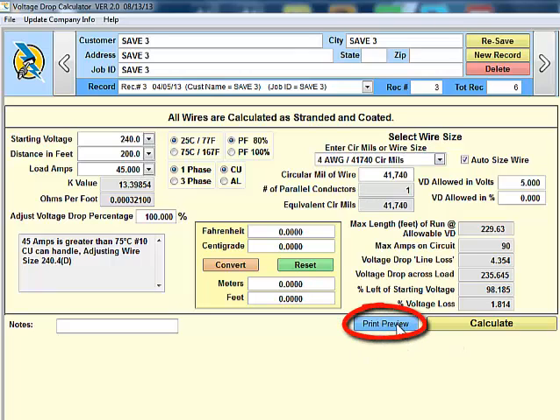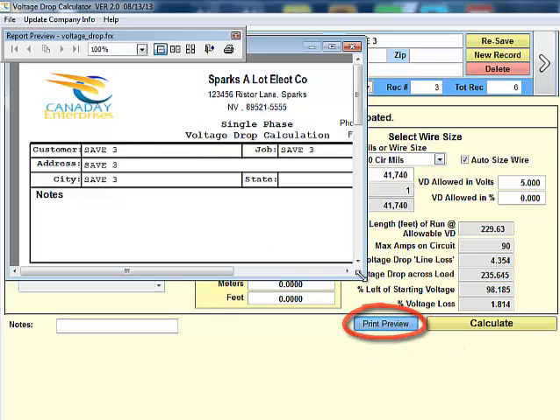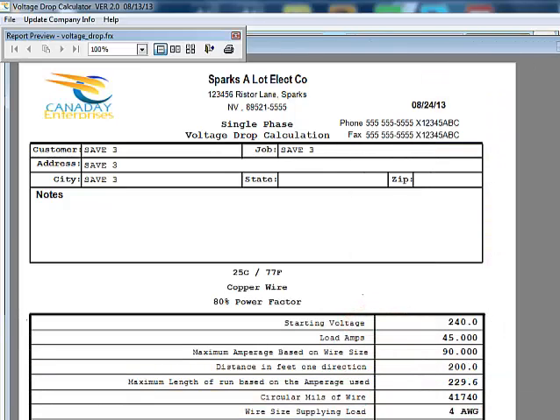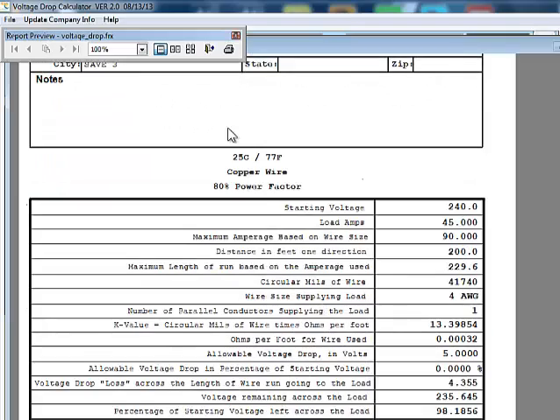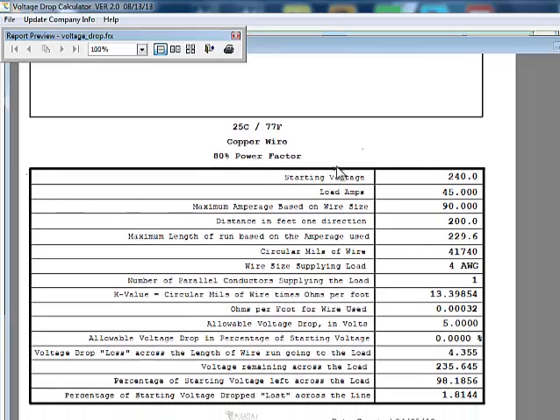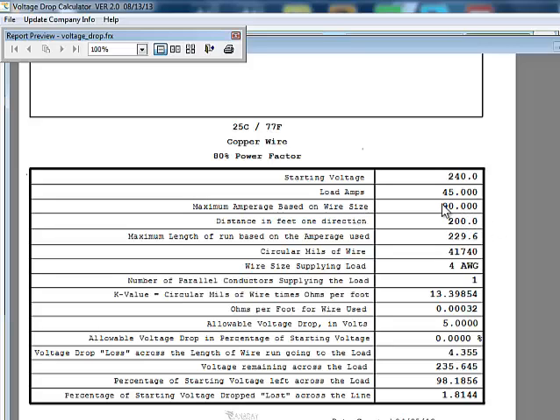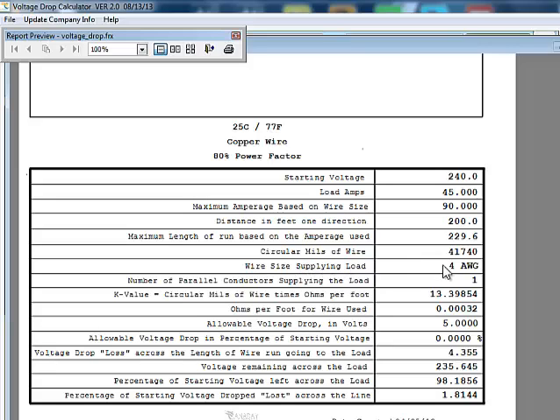If we wanted to do a print off, we could do a print preview. And now we can see what our print off is gonna look like. Our company name, our customer information and details about the wire. We're using copper wire at an 80% power factor. We have a starting voltage of 240, we start off with 45 amps. We want to maintain maximum amperage based on the wire size is 90, so that wire size allows 90 amps but we're trying to maintain the five volts for the whole distance.